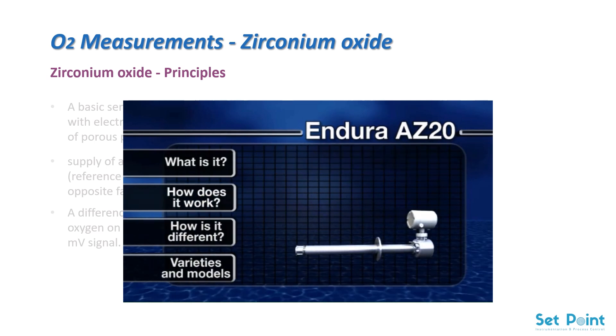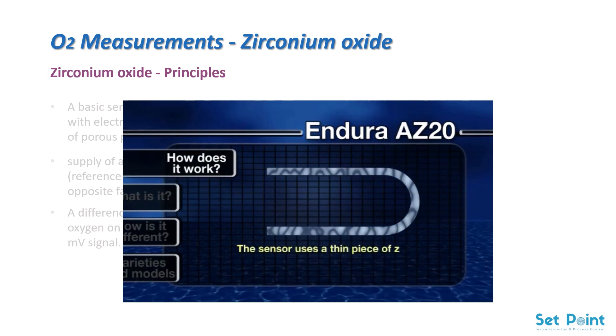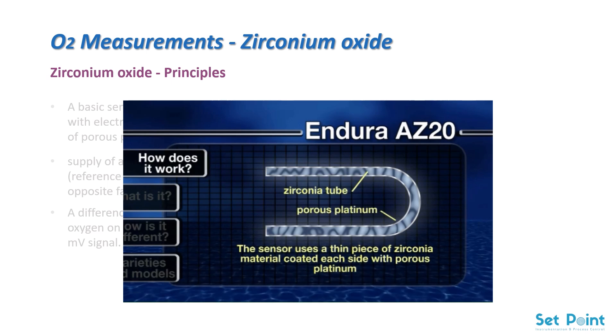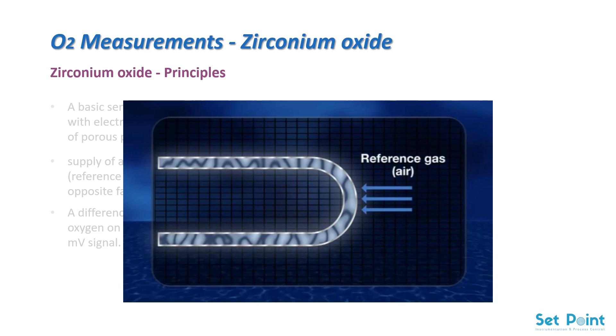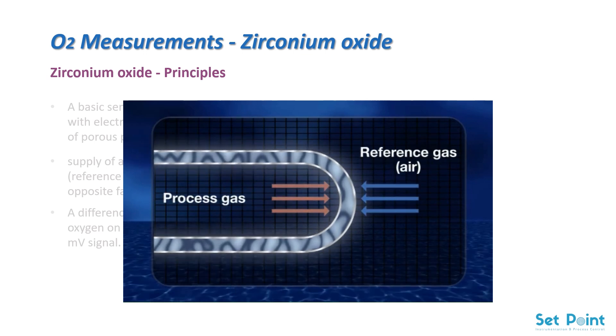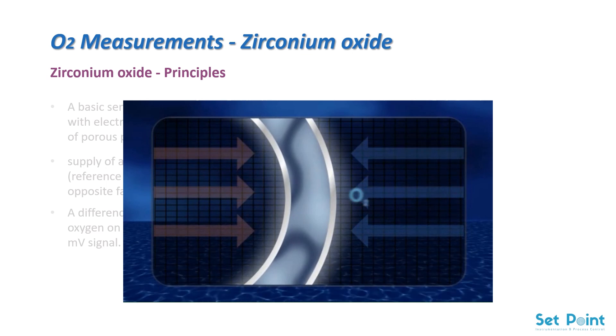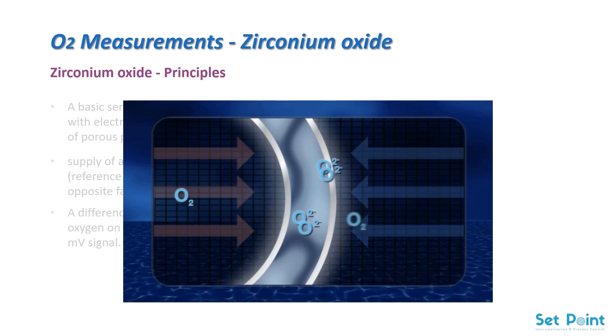How does it work? The Endura AZ-20 sensor uses a thin piece of zirconia material coated on each side with porous platinum. Air is supplied to one side as a reference gas to provide a constant oxygen concentration, and the process gas is presented to the opposite side. The platinum acts as a catalyst in the presence of oxygen gas, converting molecular oxygen to oxygen ions, which can then migrate through the solid zirconia electrolyte.